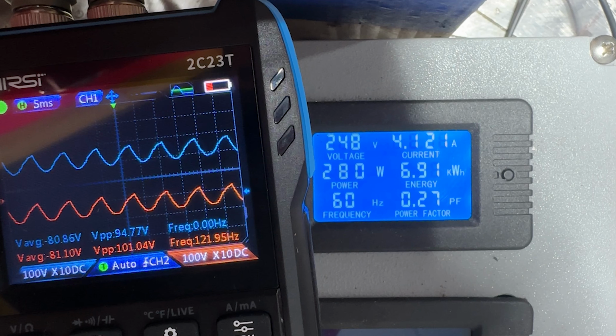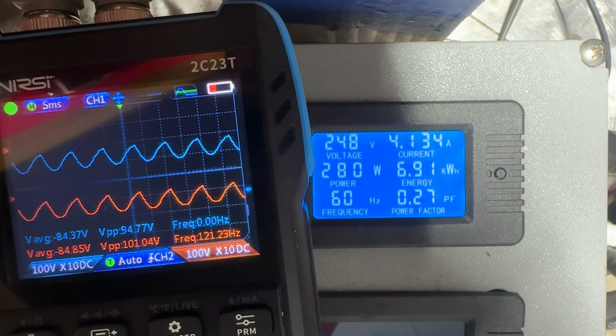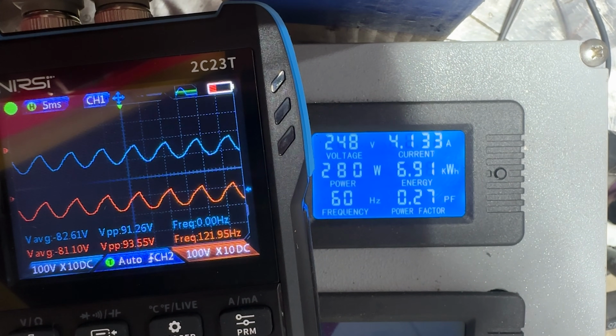So that is why that reactor or choke is put on after the bridge rectifier, because it's going to completely clean that dirty waveform of DC and make it more or less a straight line, consistent voltage. And we'll look at that in real time now. So the orange-red line is the input to that choke, and the blue line is the output. And once I strike an arc, you're going to notice how it more or less changes to straight DC that's very clean. So let's watch that in real time.